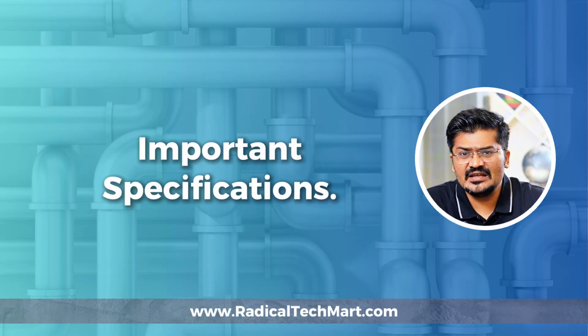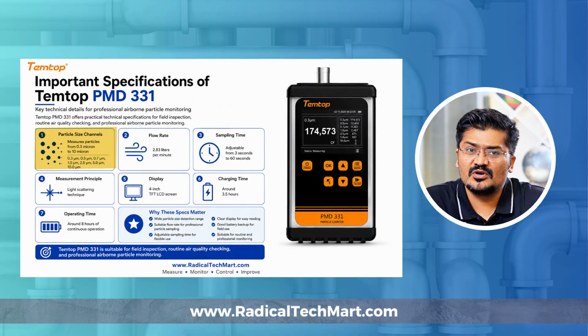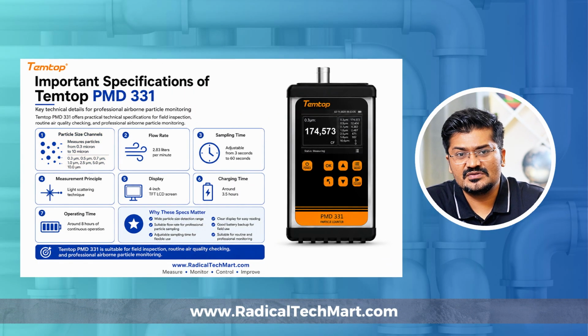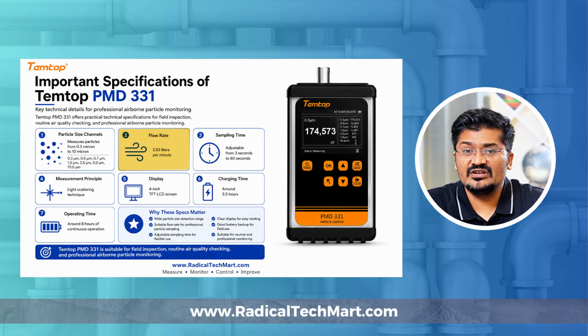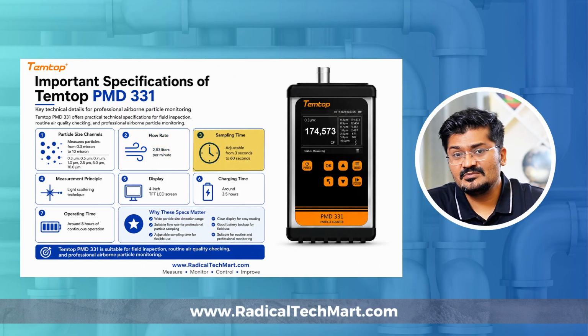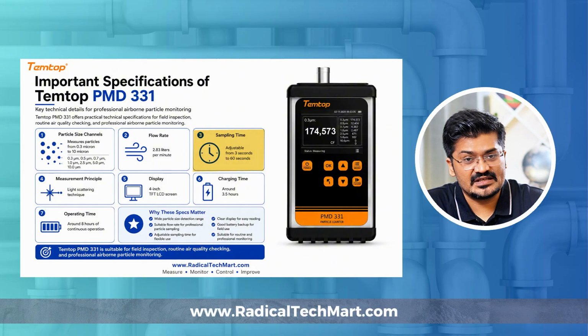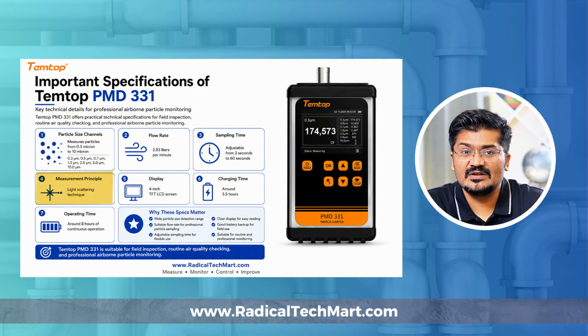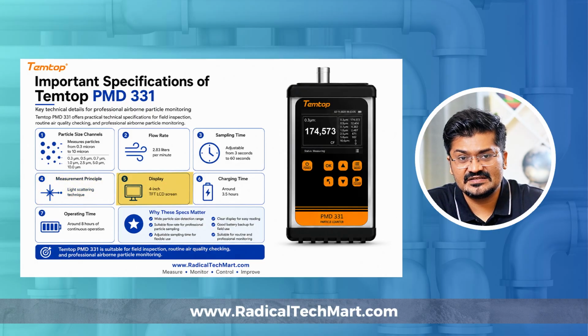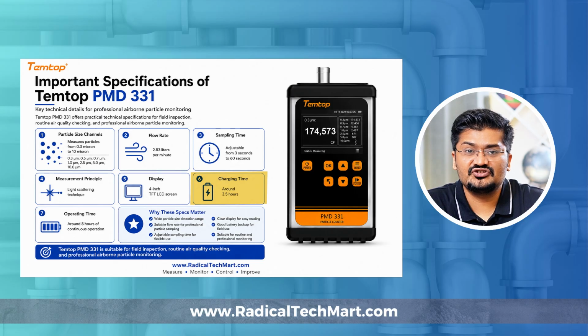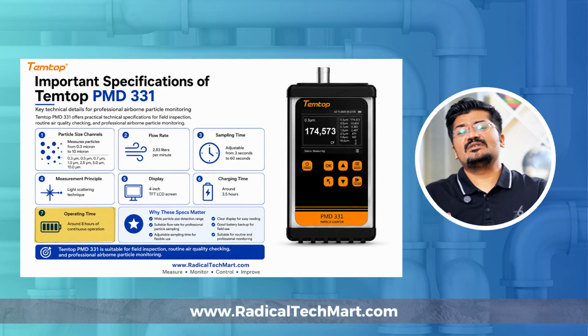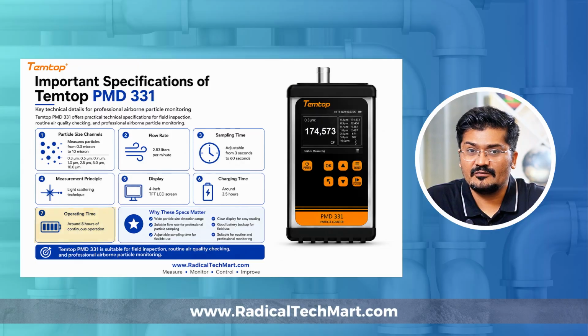Now, let's quickly understand the important specifications. The particle size channels are 0.3 micron to 10 microns. The flow rate is 2.83 liters per minute. The sampling time can be set from 3 seconds to 60 seconds. And the measurement principle is light scattering technique. The display is a 4-inch TFT LCD screen and the charging time is around 3.5 hours. And operating time is around 8 hours of continuous operation. So it is suitable for field inspection as well as regular air quality checking.